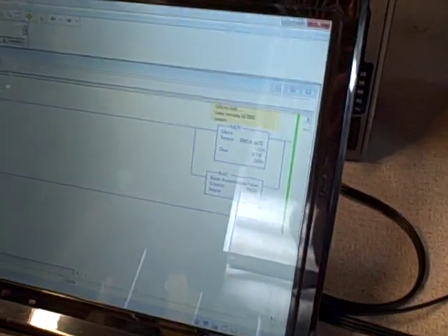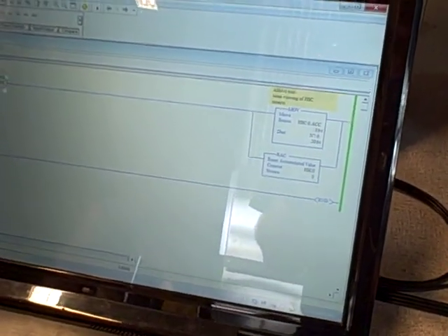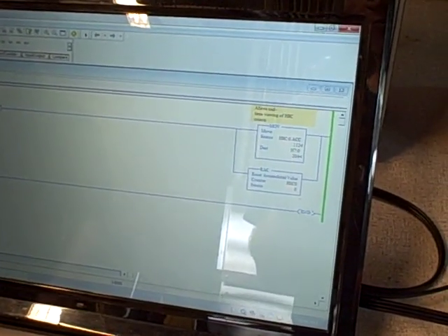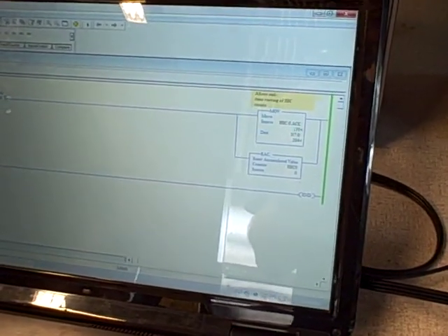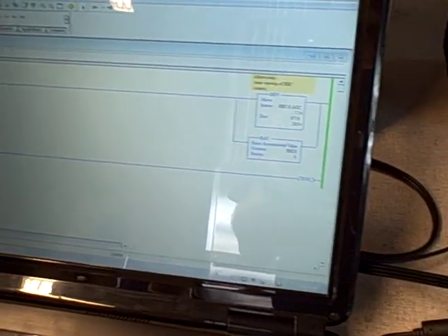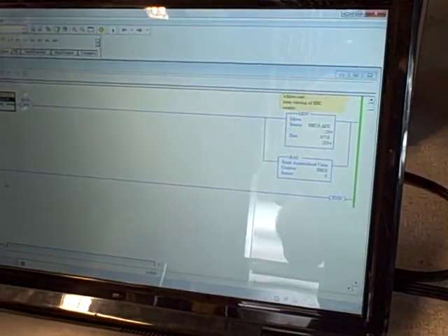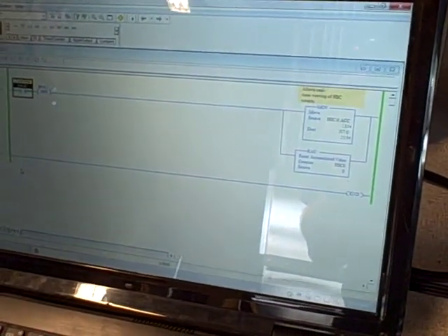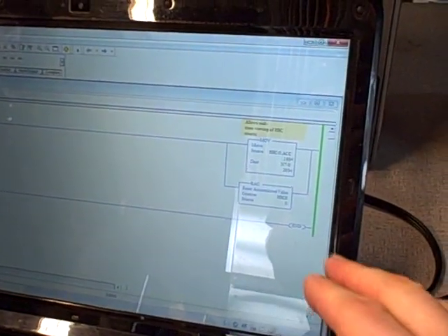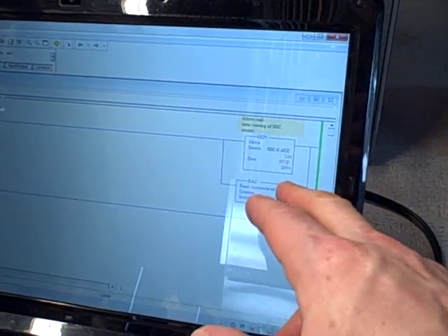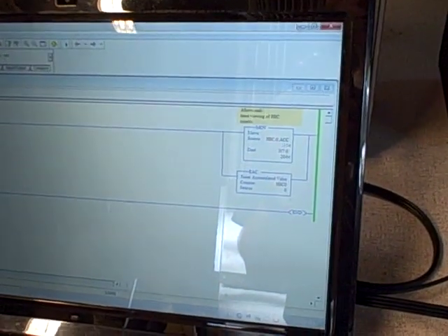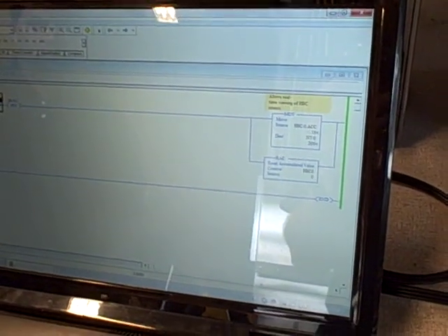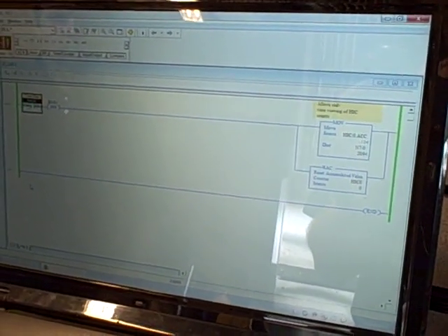We're doing this because we're eventually going to use this kind of a program to interpret the pulses from a turbine flow meter measuring airflow. And those pulses come into the PLC pretty quick, quicker than the program can actually scan through, hence the need for a high-speed counter. This is our first real working test program we have. It's very crude. It does nothing but take that high-frequency pulse train and scale it into a small value, which we can read in the N7 register. But later, this will be used to measure flow rate through a pipe and to be part of a flow control system. That's pretty neat to see the high-speed counter operation of the MicroLogix 1100.